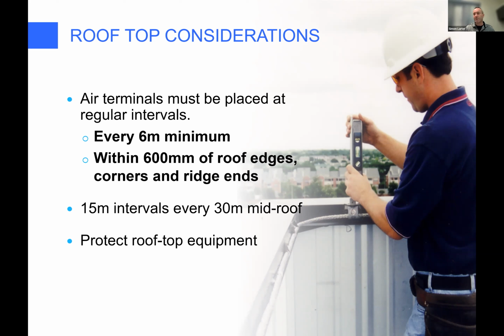If we have a parapet coping, for example, the Bow Tower here in Calgary has parapets sometimes that are 30 inches wide—about 750 odd millimeters wide. In that case, you're not going to be putting the lightning rods on the inside of the parapet like you see in that image. You're going to have to glue lightning rods to the top of the parapet. Was that done in Bow Tower? No, it wasn't, but that's a whole nother story.